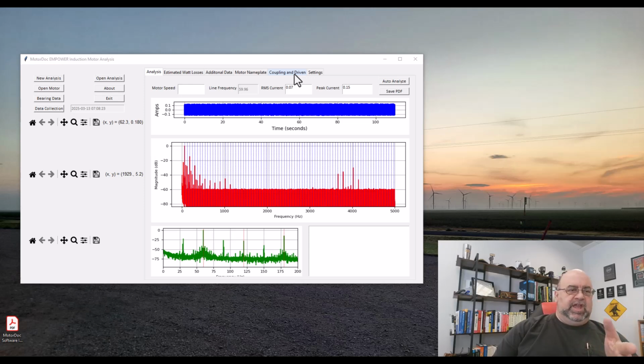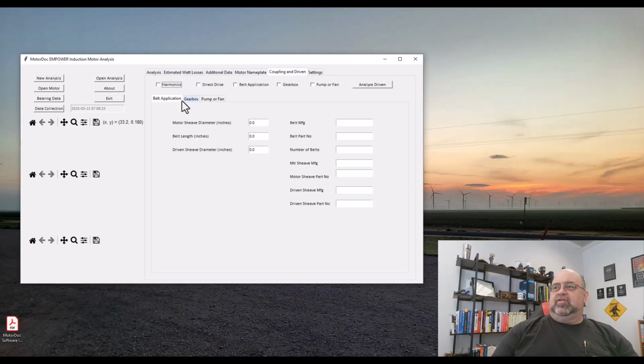The further you get that current sensor away from the surface of the machine, where the actual surface currents are, not flux from the winding, or flux from the air gap, or flux from the core, sorry, that motor's in a Faraday cage. You're reading off the surface on the outside of the Faraday cage. So you're not reading the same thing. You are reading basically noisy filtered data. And let's see what that noisy filtered data looks like still.